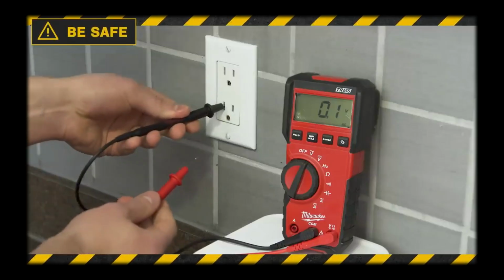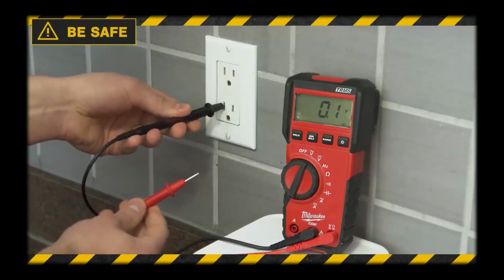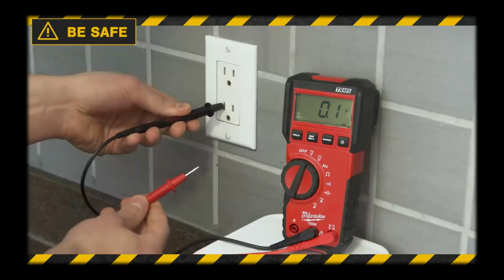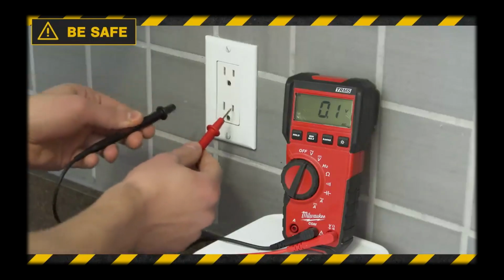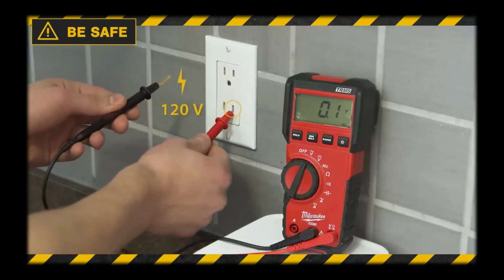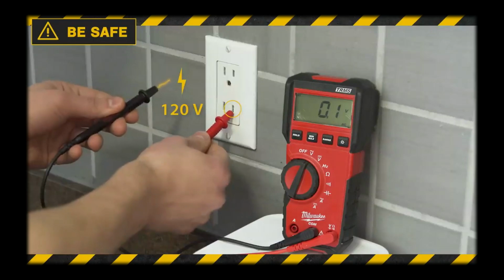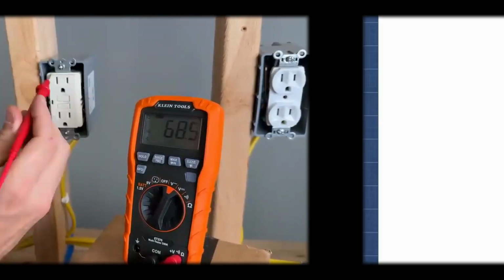When testing live voltage, it's essential to use caution. Always start with the neutral wire first before connecting to the hot. If you connect to the hot side first, the other multimeter probe becomes energized, increasing the risk of shock. So why is that?